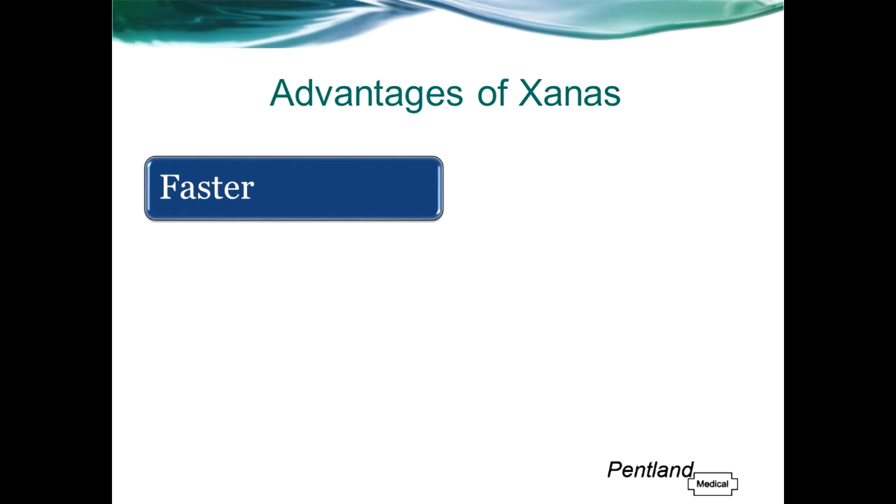So what are the advantages of Xanas over other methods of pulse oximetry? First of all, it is faster. Studies have shown that Xanas will reflect any changes in saturation up to 40 seconds faster than a finger sensor. This is because blood coming from the heart will go to the brain before it reaches the extremities, and therefore any changes in saturation will be shown by Xanas before they would be on a finger sensor.